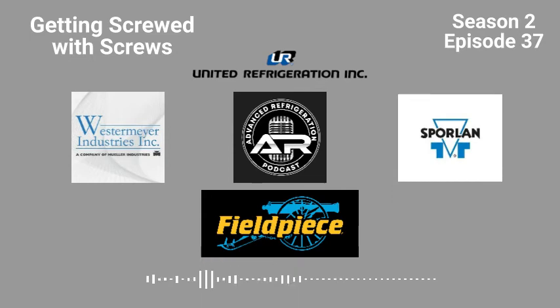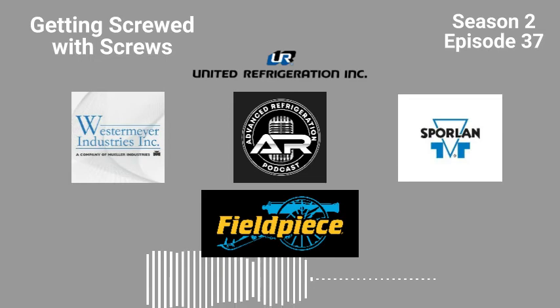Well, fortunately enough, it's on a rack, so it's not like it's controlling any of that on a self-contained unit. A single unit would be a disaster. An absolute disaster on a single unit. Unless it was loaded up with like a hot gas bypass valve, desuperheating. Yeah, but they don't seem to ever put that in.